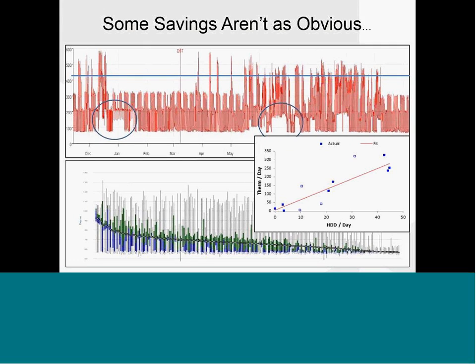So that's a good opportunity for energy savings that without this type of information you wouldn't be able to identify. The second chart looks at the thermal side—same buildings, so the demand chart and this thermal chart are the same building. Each dot is supposed to be fully filled in blue, hovering around that linear regression line. What happens is they start to move away from the regression line, which gives you an idea of where there might be savings opportunities. When they start to go from dark blue to light, that tells you there's an anomaly and something's going on.